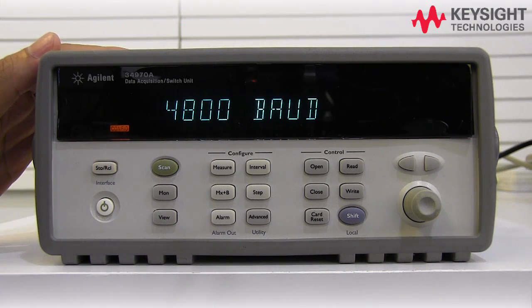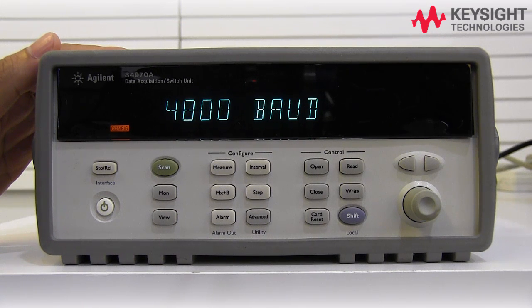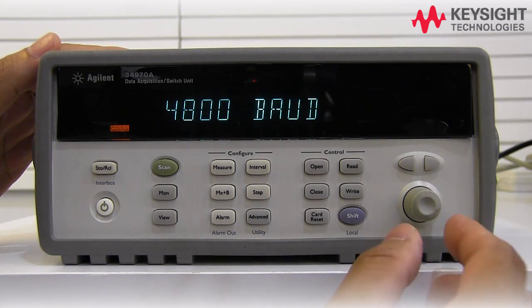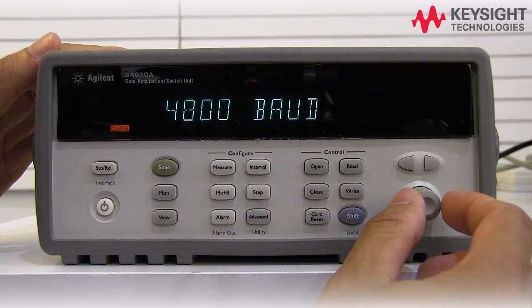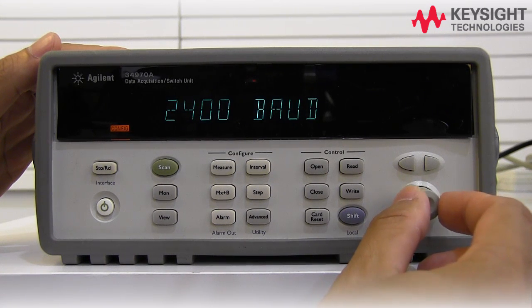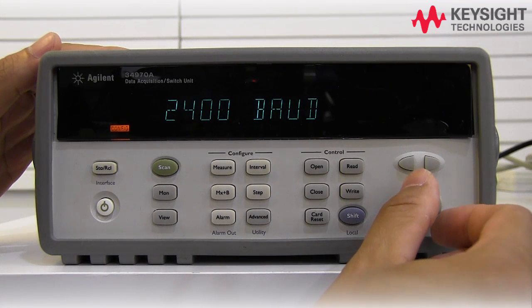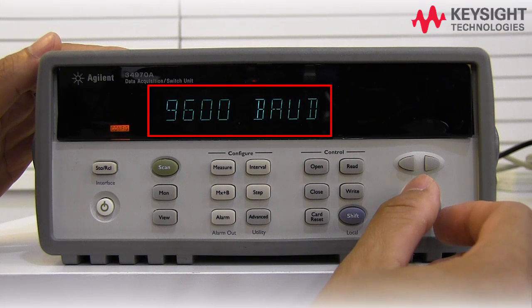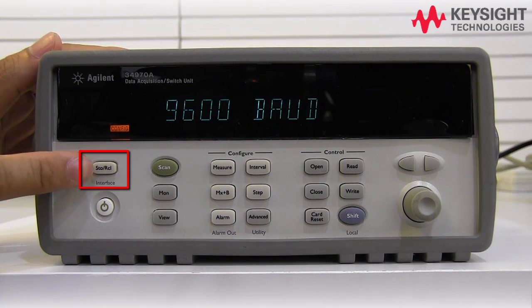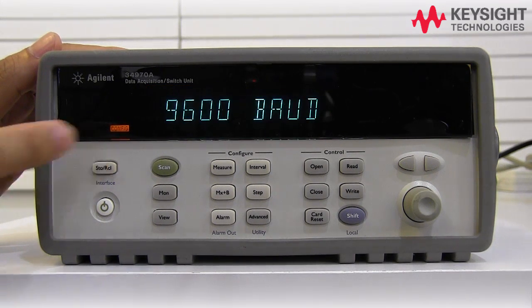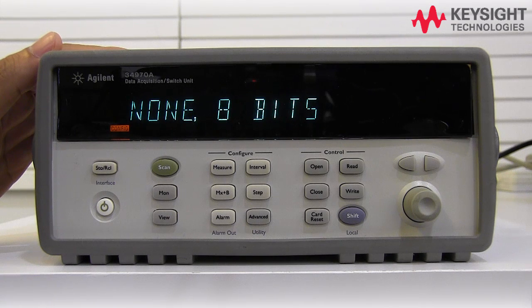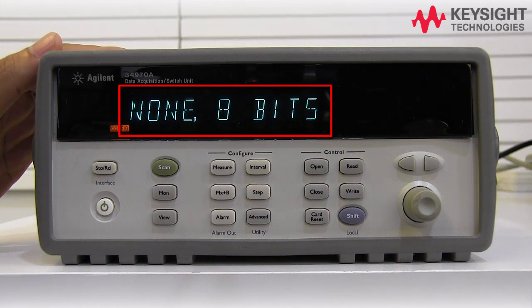Next is the Baud Rate. There are a few Baud Rates above. For this, we choose 9600 Baud Rate and then we press this button to save the setting. For parity, we choose none, and then for the bits, we choose 8 bits.